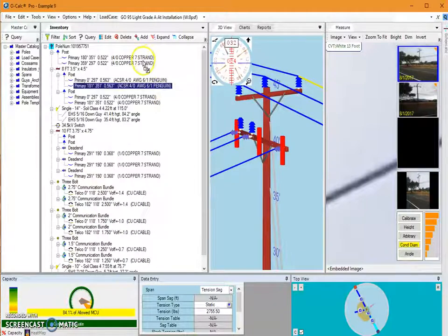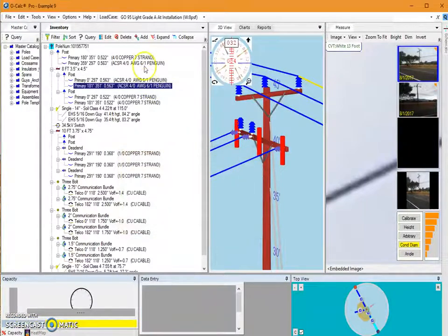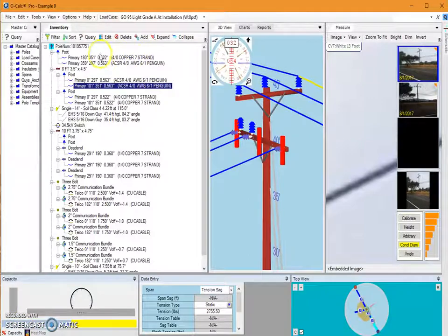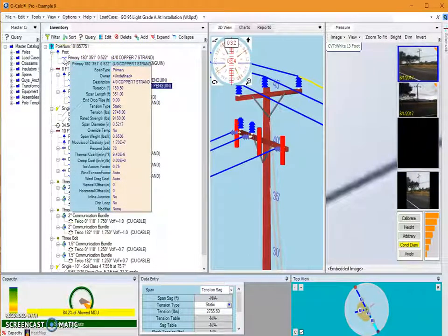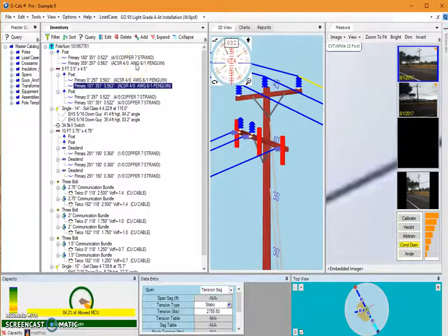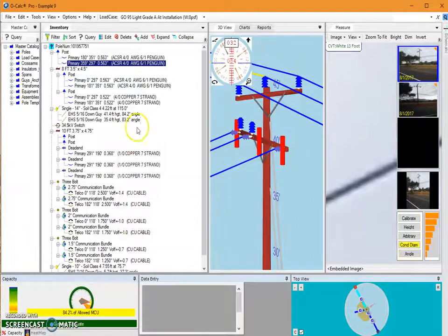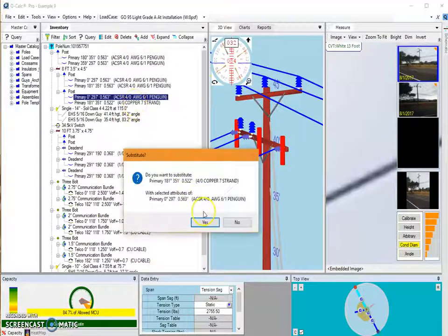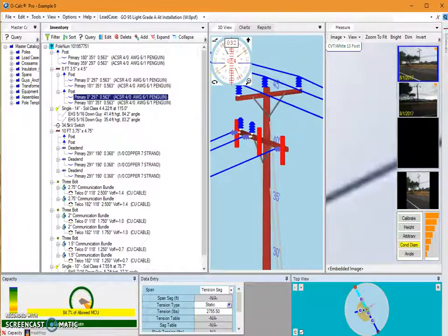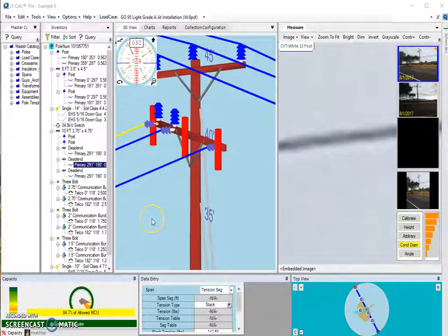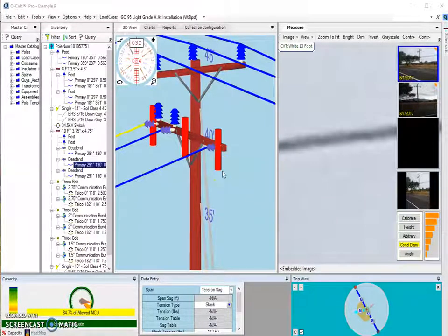Alternatively, you can go in and replace all the spans you need to. The span I originally started with had a diameter of 0.52 inches — not very far off, but a little bit smaller than reality, so it does make a slight difference on capacity utilization. Once I replace all of these I can see that I'm at 84.7%. That would conclude this video as Part 1 of how you can use the CVT tool and DMT technology. I will continue this example in a Part 2 video.